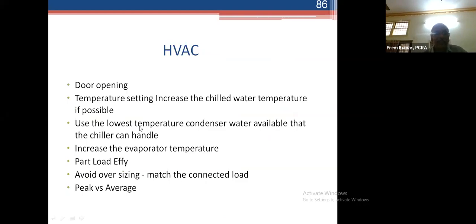The HVAC, again, sizing is very important. Sizing it for the normal load rather than the peaking. So reduce the condenser temperature, increase the evaporator temperature. So while sizing, consider the peak and average, as we discussed earlier. Consider multiple units, or at least look at the hiring concept, going for average thing.